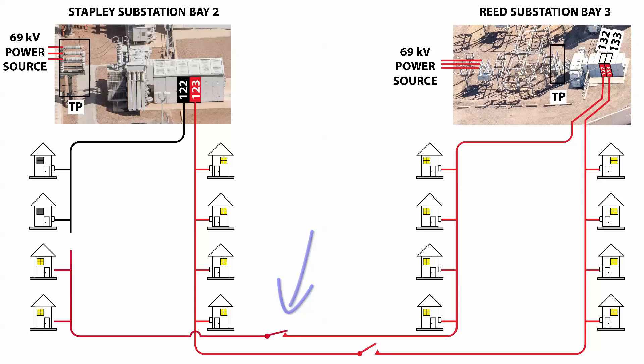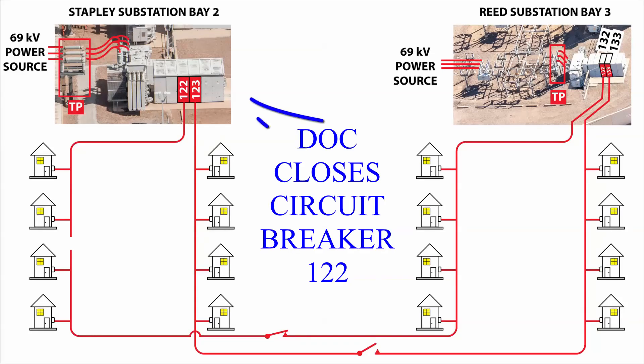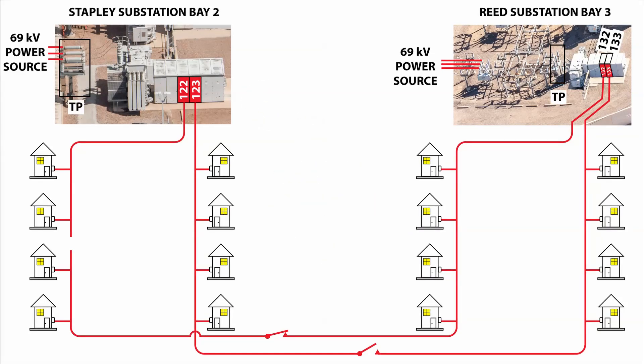Note that Reed substation is now supplying power to some customers who had previously been supplied by Stapley. Finally, DOC closes circuit breaker 122 at the Stapley substation, and since the fault has been isolated from the power system, circuit breaker 122 remains closed. Now all 800 customers have power restored to normal, but the original fault condition still exists and must be repaired within a few months, since the looped system is vulnerable to a longer-duration outage affecting more customers if another fault occurs after the normal open has been closed.